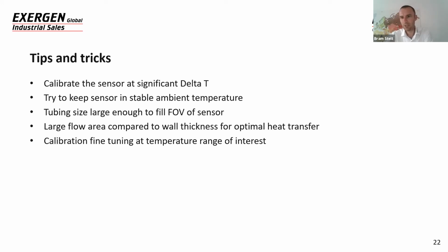It's advised to take tubes that have a relatively thin wall compared to the flow area, because temperature changes in the fluid need to be transferred to the surface of the tube as quickly as possible. And if you have a very thick insulating wall, that's not the case. So a thin wall tube is preferred when using the heat balance method. And once you've done the initial calibration, as explained in the video, test it, and you can also do some fine tuning on the set screw to maximize efficiency within your temperature range of interest. So these are the tricks that we have.